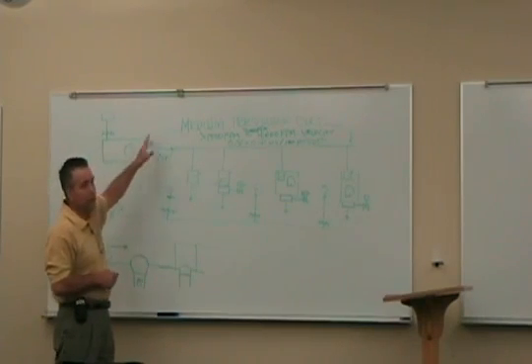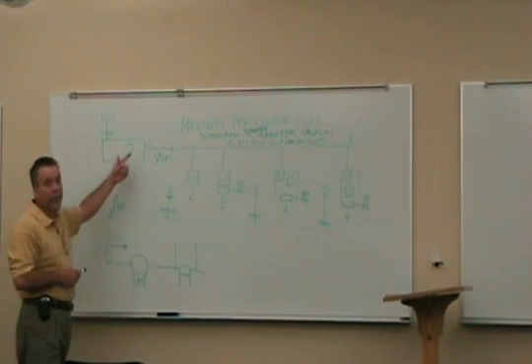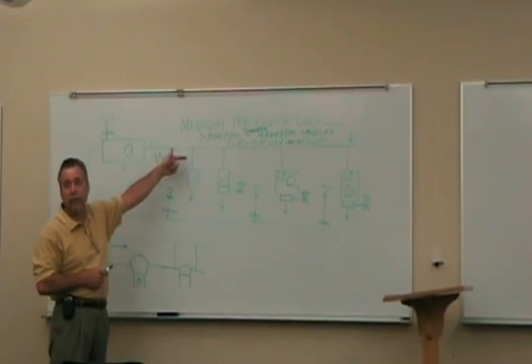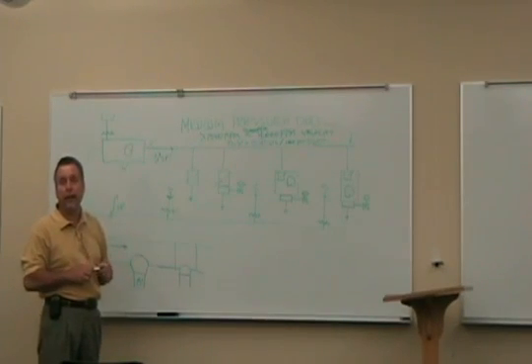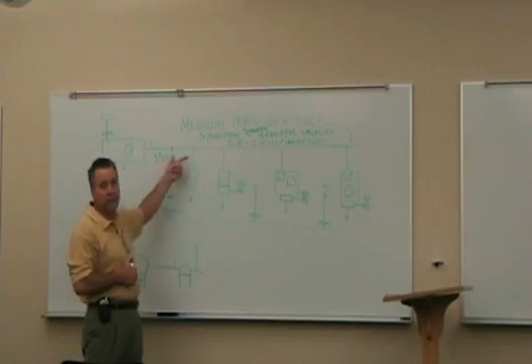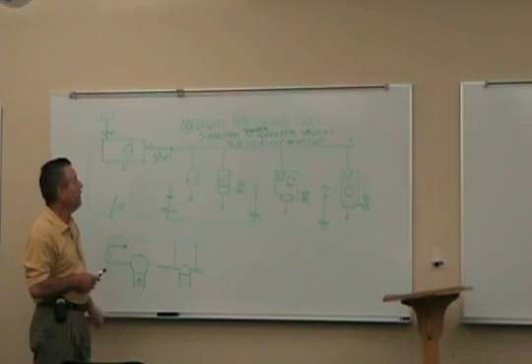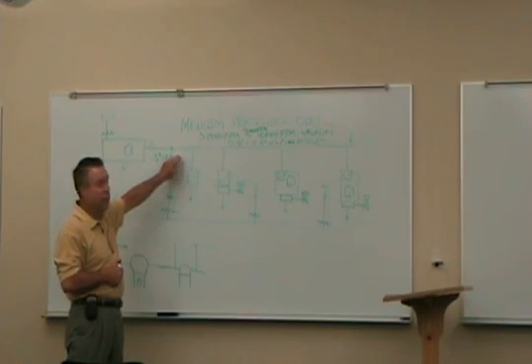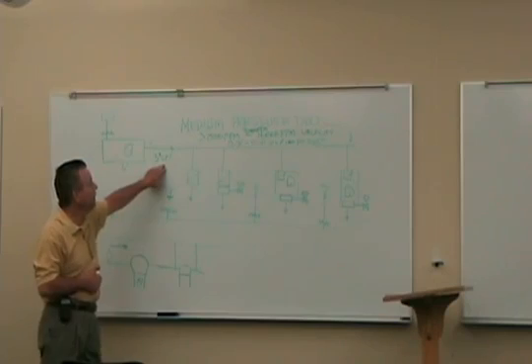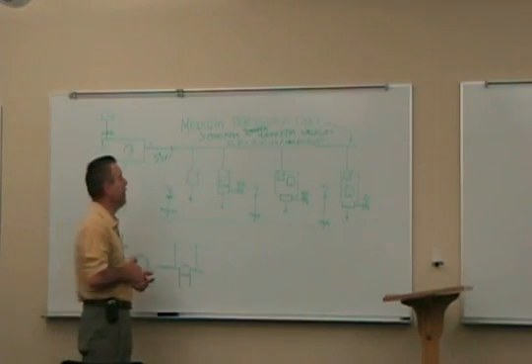And then you get to a certain size duct, I don't know what it is, but let's just say it's 4 feet by 4 feet. You may actually see 1/2 inch EMT conduit in this duct to stabilize the duct. That's perfectly legal. It's an appropriate design allowed by SMACNA, but it's just odd looking. And generally they just use 1/2 inch EMT conduit. But all of that has to do with the charts that are listed in SMACNA and how you build this duct. And it's based on the pressure range that you want to maintain, and then the contractor has the choice of what gauge and what kind of reinforcement he wants to use.